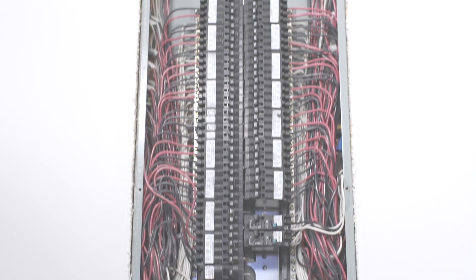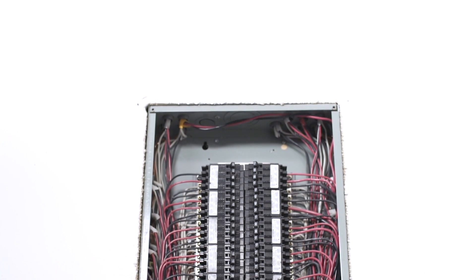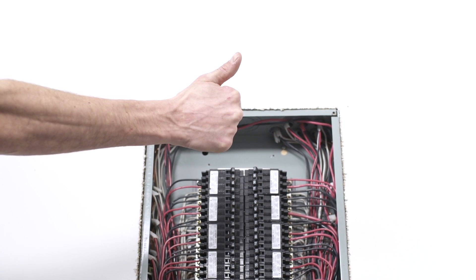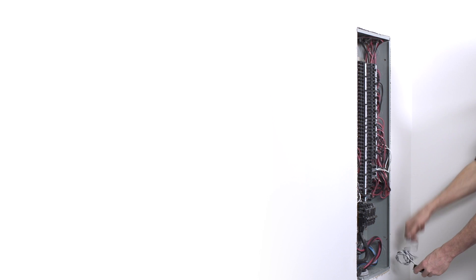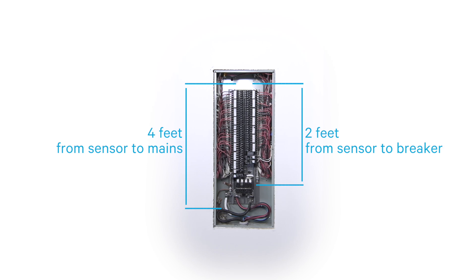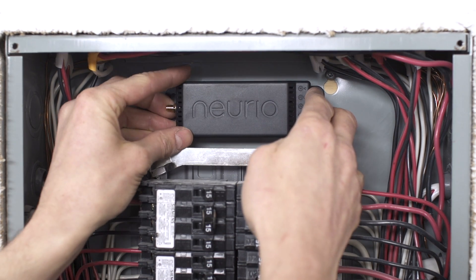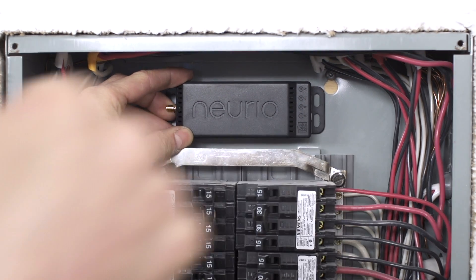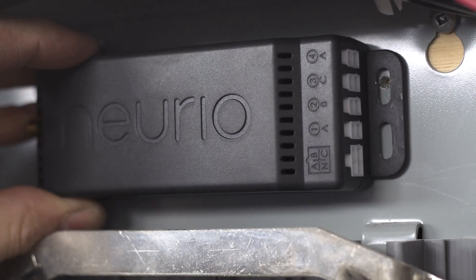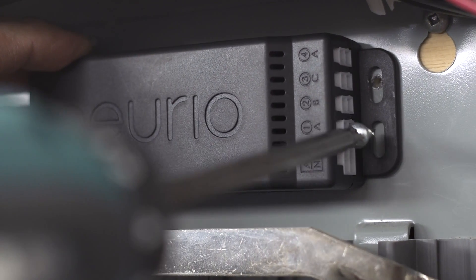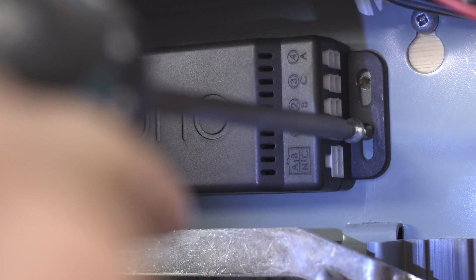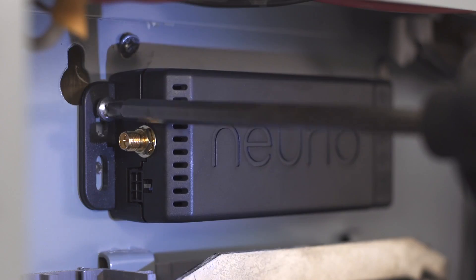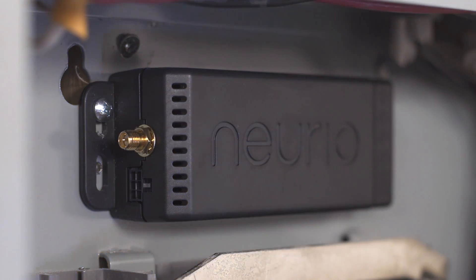Now let's mount the Neurio sensor. Find a convenient location within the panel. Make sure you allow room for the four-foot current transformer leads and the two two-foot voltage cables. Also, try not to mount the sensor too close to the side of the panel. Using the self-drilling screws included in the package, secure the Neurio sensor in place. It might take some pressure for the screws to drill the metal panel.